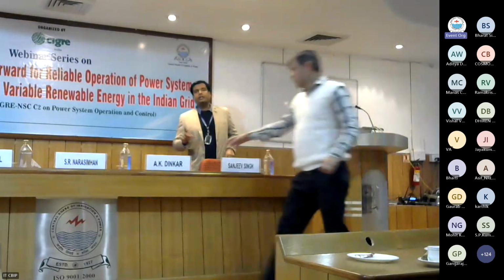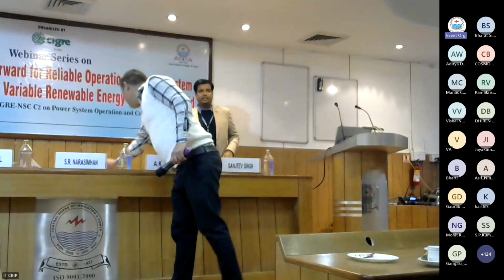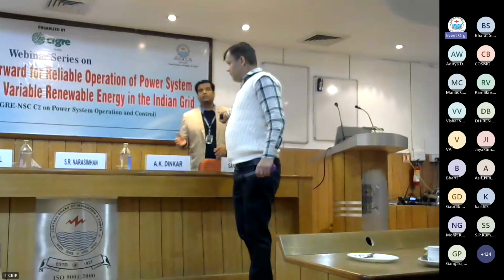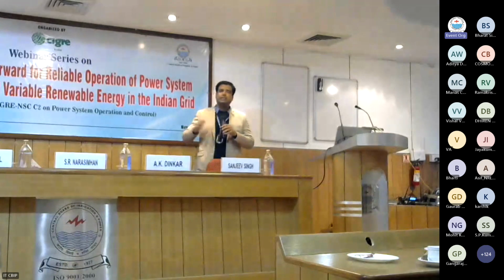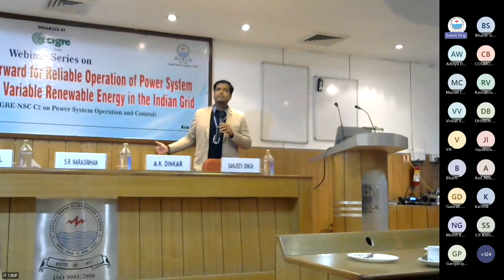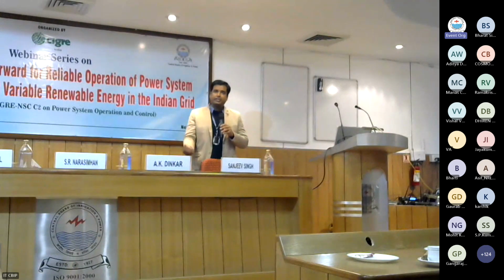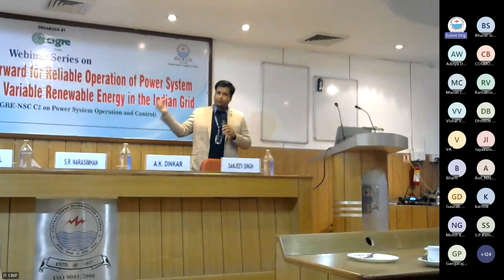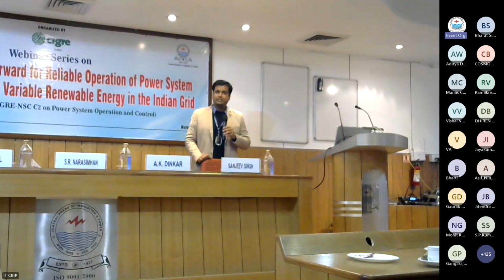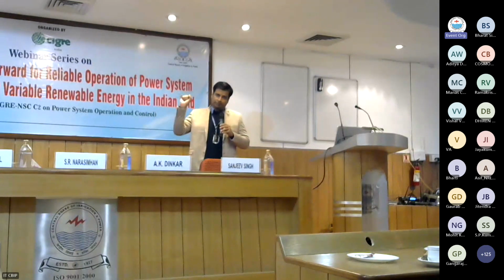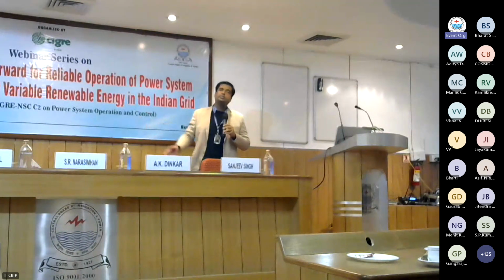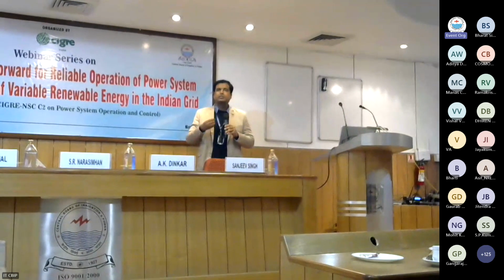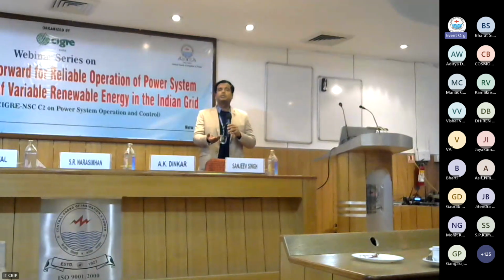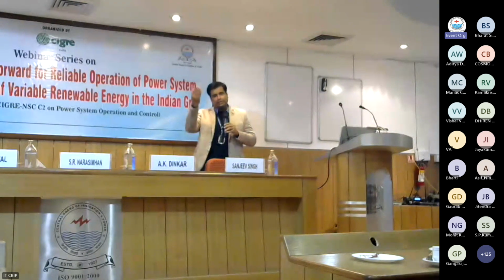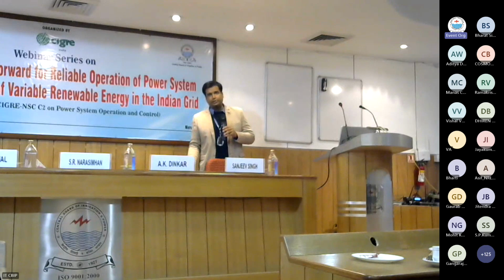Yes, one fault at the RE-rich pocket resulted in the reduction of generation of other RE plants which were far off from that plant. That resulted in the generation loss. So it is not exactly that the line tripped and its generation tripped. It appeared as a voltage dip to the complete RE pocket, and that voltage dip was observed across all the pooling stations. Since the pooling stations observed that voltage dip, the RE plants connected behind those pooling stations treated it as a signal to enter the low voltage ride-through zone. They reduced their generation, and the generation got reduced.